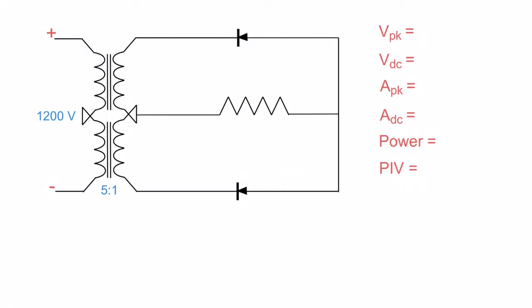Now let's start seeing what we can do with the voltages here. I've got 1200 volts across, so I'm going to have 600 there and 600 there. So we've got 600 volts across each winding. I've got a winding to winding ratio, if you remember from transformers, of 5 to 1. So if I have 600 here, that means I'm going to have 120 volts over on those windings, on my lower voltage windings.